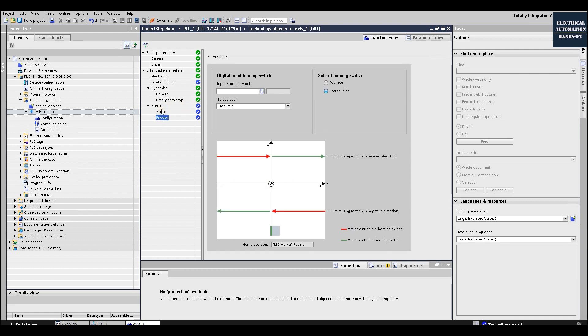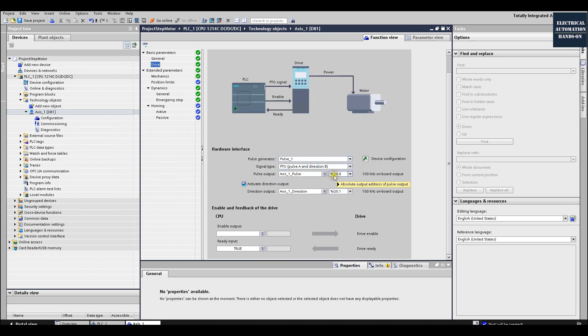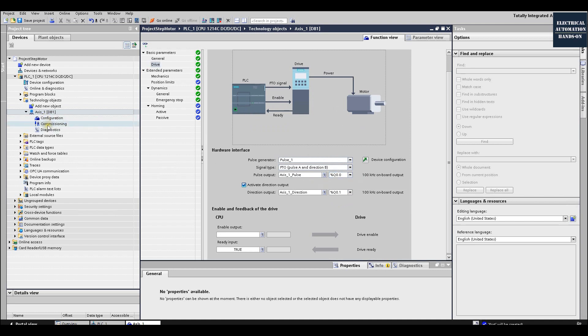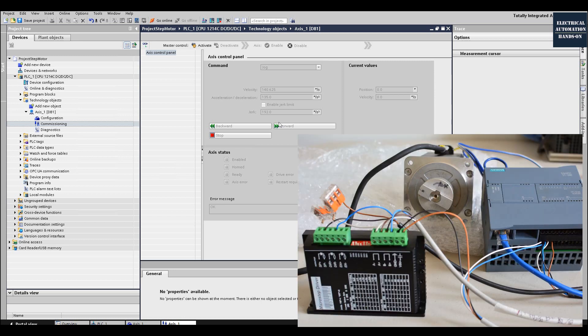More importantly here is the drive configuration — which hardware channel delivers the pulse output. I'm using Q0.0. Now I can download this configuration, then use the commissioning control panel to control the PLC and deliver pulses to control the stepper driver and stepper motor — all without using any program. This allows me to verify if the PLC can deliver pulses, if the hardware wiring is correct, and if this driver can control the stepper motor properly.